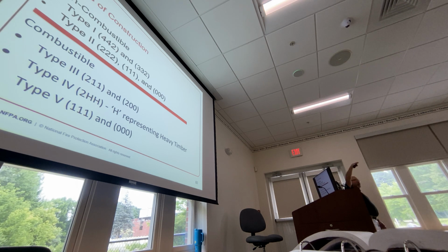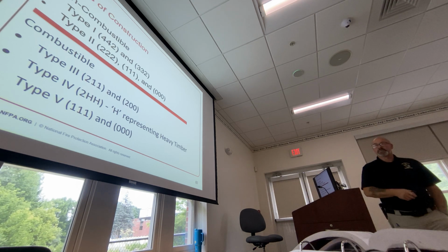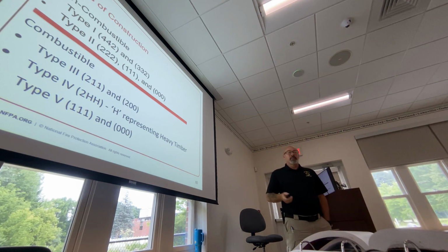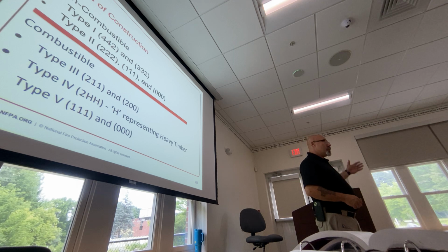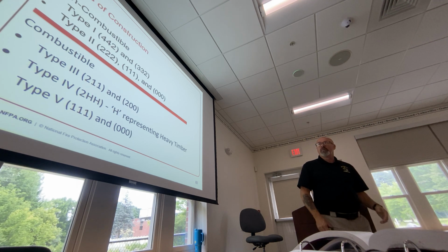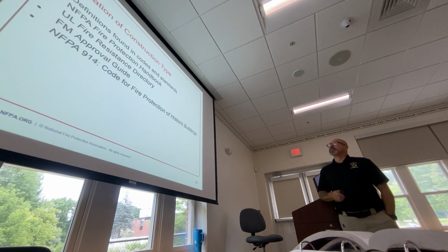You're not doing 5/8 fire code sheetrock on the ceilings. So most of your sheetrock is just, maybe you're doing 5/8, but it's not fire rated. But for the most part, you're doing 1/2 inch sheetrock, so there's no fire resistive rating at all. There are certain occupancies that require that type 111, that 5/8 sheetrock, to protect your structure, protect your exterior walls. So we'll talk about each individual one here shortly.